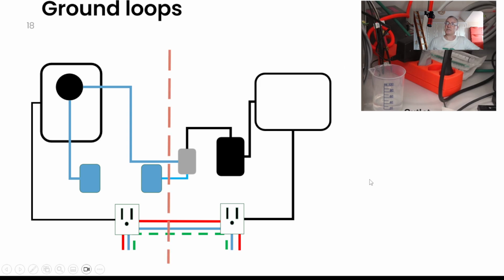If I split this system in two, you won't get ground loop problems if the grounding on this side of the system is the same as the grounding on this side of the system. But I have seen this happen in the past where these two systems are not at the same ground point. If one of these systems has, for example, a slightly higher resistance to ground than the other side of the system, then the grounds are not together, they're actually separated. And when they're separated like that, you can have the flow of current.